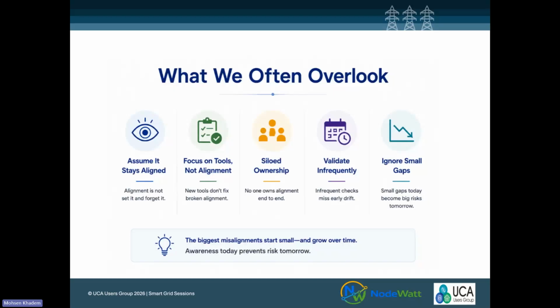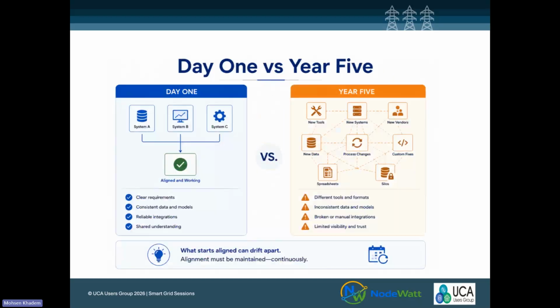As I said, that is the key. If drift happens the day after go-live, try to document it, capture it, talk to the team, and fix it early. Day one versus 5 or 7 years later - that is the situation I was talking about. If you find yourself in that situation, which happens if you don't take care of alignment, you will. That's the reason power utilities change vendors every 7, 8, 10 years.